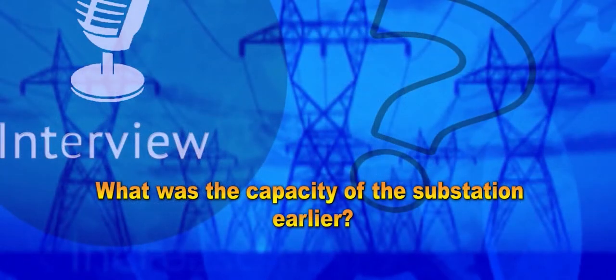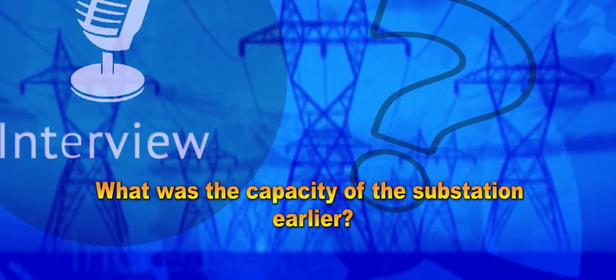What was the capacity of the substation earlier? Right from the beginning, this substation is 2 by 60 MVA transformers, which means 120 MVA, equivalent to 96 megawatts. So when we lost one of the transformers, our capacity dropped at that time to 48 megawatts. Now with the replacement of the same capacity, we are back to 96 megawatts.